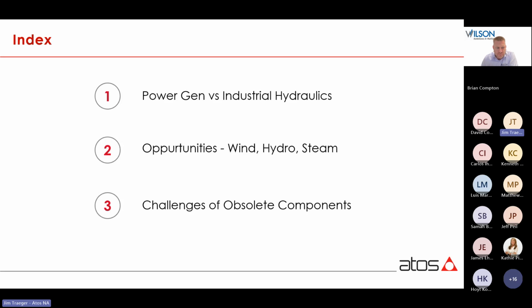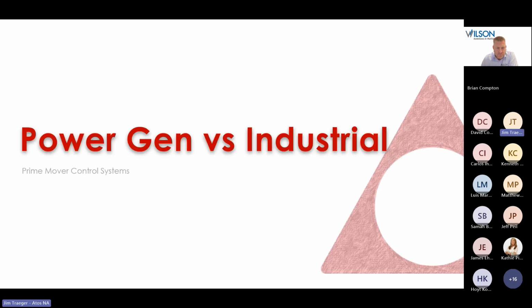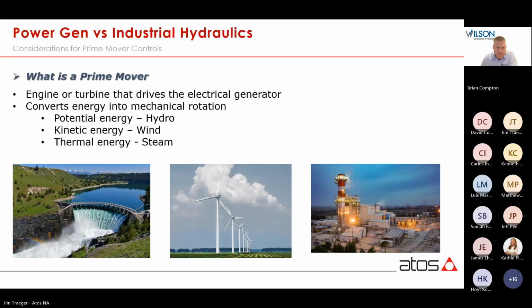My name is Jim Traeger, and today I'm going to start off showing you some important differences between the hydraulic circuits used in power generation and the ones more commonly used in industrial applications. I'm going to focus on circuits used for prime mover controls, since they're the most critical and unique in power generation hydraulics. What are prime movers? Broadly, a prime mover is an engine or turbine that drives the electrical generator. More specifically, it's the components that convert the available energy into the mechanical rotation used by the generator. In hydropower, the turbine converts the potential energy of water plus gravity into mechanical rotation. In wind power, the turbine converts the kinetic energy of the wind into mechanical rotation. And in steam power, the turbine converts the thermal energy of the steam into mechanical rotation.